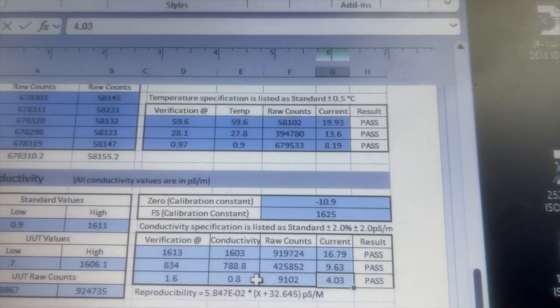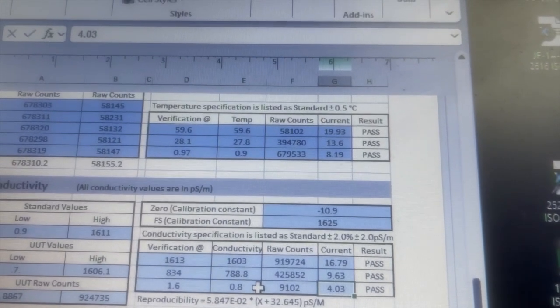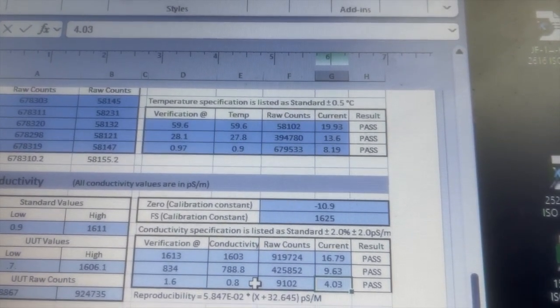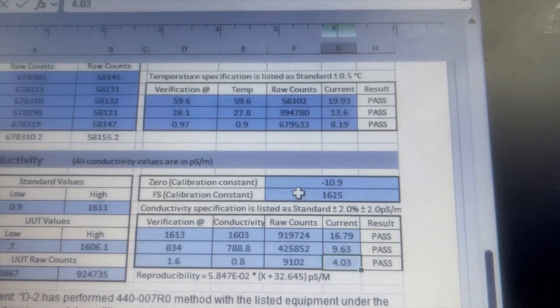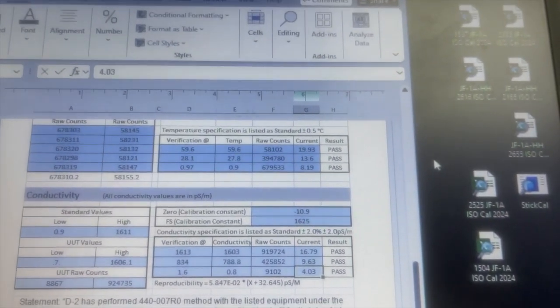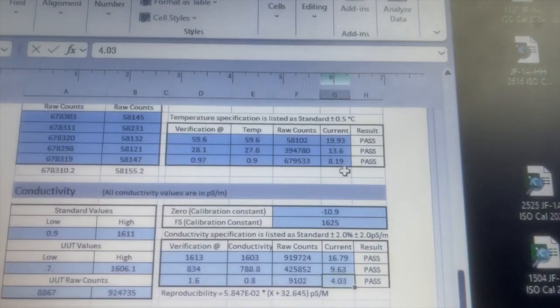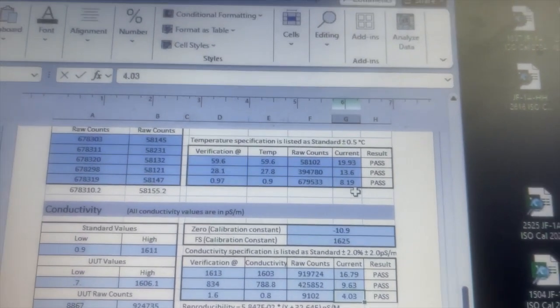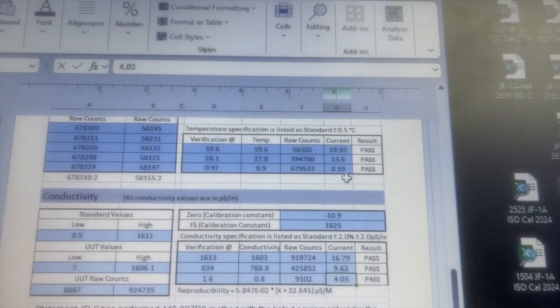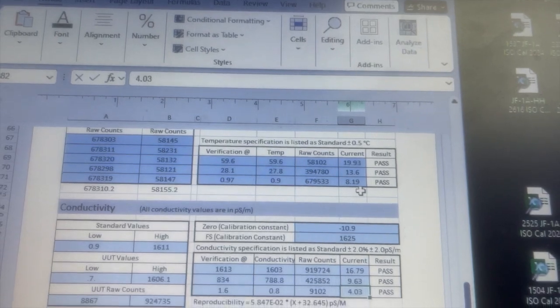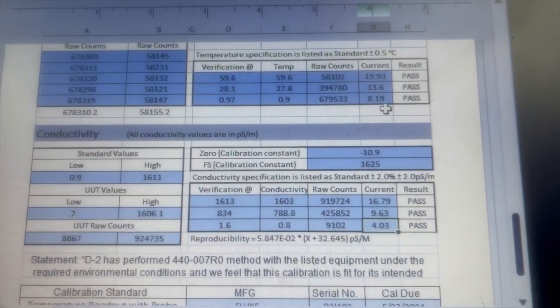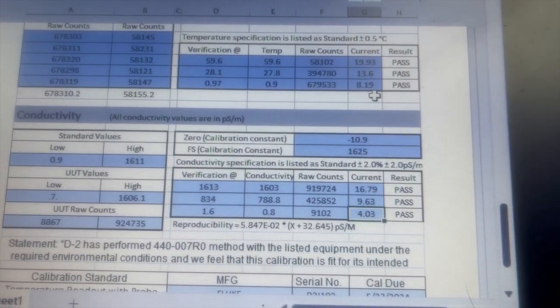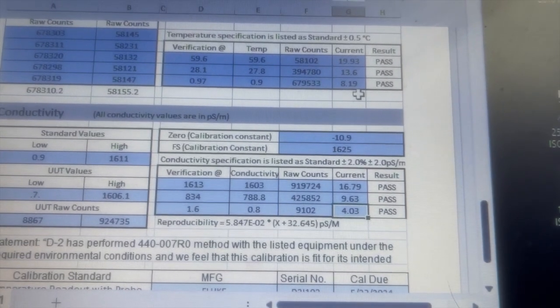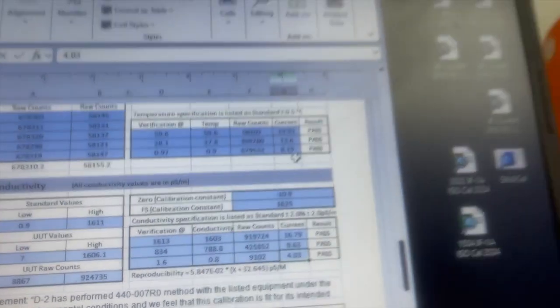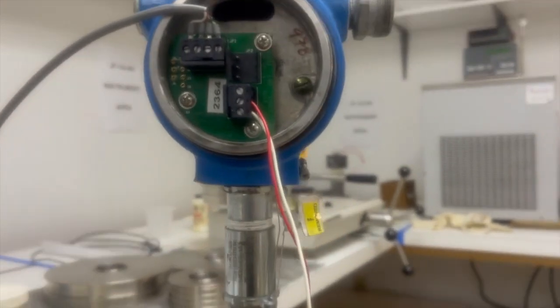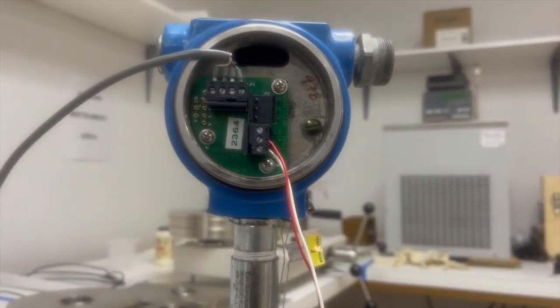We've passed the temperature verification and calibration. And the sensor has been verified and calibrated and now can go back into use in the field for the next year. And you verified it against NIST traceable standards, all with the kit that we can provide you. So if you would like to do this calibration yourself in the field, instead of sending your equipment to us to calibrate, you can calibrate the inline sensor on your own with the kit that we will sell to you.